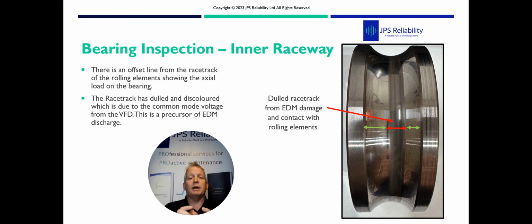On the inner raceway, you can see the dullness of the track, which is due to common mode voltage, and you can see it's slightly offset. Whether something was in the magnetic field, or the coupling was not perfect, you can see the bearing was slightly offset. We got a common mode voltage, but it is discharging through the outer race and trying to get down to earth, back to the transformer.